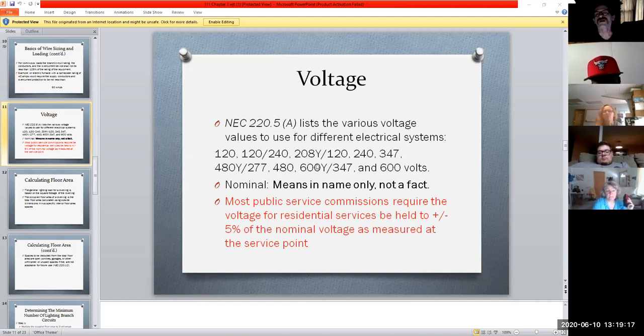And they'll have it laid out for the power distribution, depending. I mean, commonly, you're not going to have these big boys down here. We don't have homes where we have 600 volts on average. Usually what we're dealing with is right down in this range, the 120, the 120/240. Sometimes, certain commercial things like stores, you might run into some of these other configurations. Usually not. And then when you get into a factory or something like that, you're going to start dealing with much higher power. But that's other considerations. That doesn't typically go with your average house. Your average house, you're dealing with these bottom two right here, more often than not this 120/240 combination.